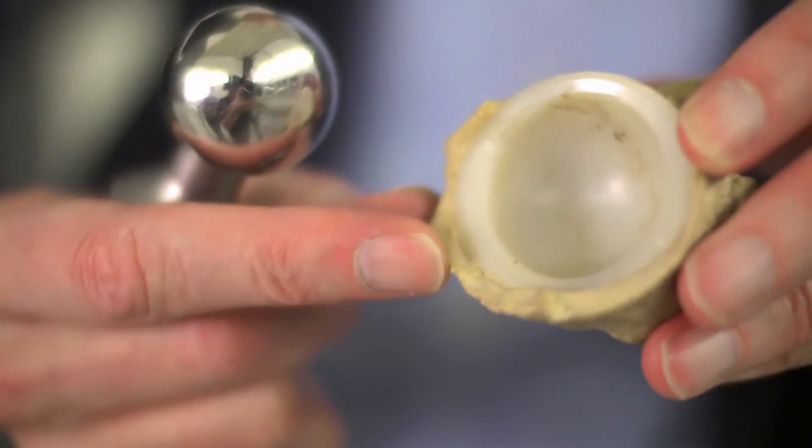One possible problem is that metal can come off this part here and deposit on the plastic here, and it can just be a thin layer of metal so you can't actually see it with the naked human eye. But what you can do is place this whole body into the Phenom microscope, image it at high resolution, and then use the X-rays emitted when the electron beam strikes it to say what the metal is. We can say without doubt that the metal from this — which is titanium — has actually deposited on there.